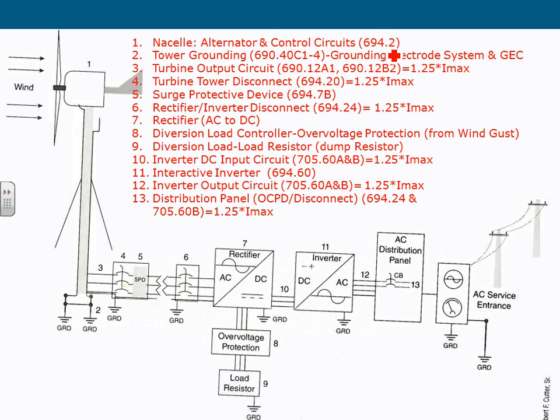And the code requires you to drive a ground rod, one option, to have a so-called, and this is technical terms, I apologize for non-technical people, it's called a grounding electrode system. You have to provide a grounding electrode system, nothing other than a fancy name for a ground rod or a concrete encased electrode, rebars. So any metallic object in proper contact with Mother Earth, we call it.